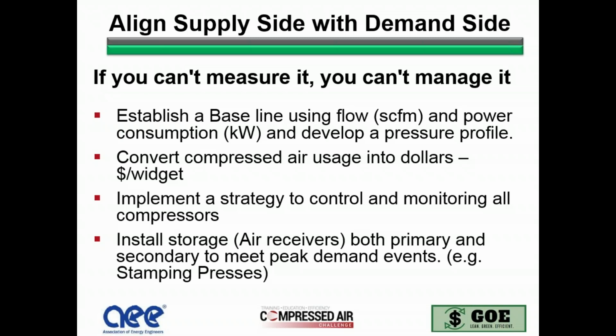In many cases, you're going to want to look at the amount of storage you have, both the primary and secondary. Again, this allows you to meet the peak demands that you have in the system. One of the examples, again going back to the auto industry, is stamping presses, which require a lot of air to stamp out sheet metal parts. They each have their own secondary receiver to help assist anytime that the press is actuating.